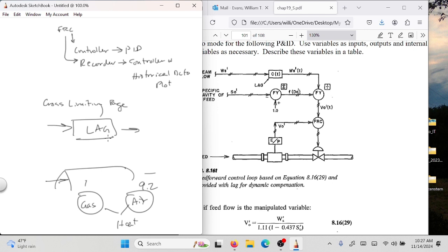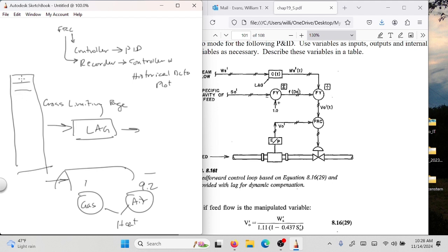How do you build a lag block if there's no such thing in your PLC? We've already talked about an instruction that works as a lag block — it's called a FIFO. Put something in, take something out, just delay it. If you want a five-second delay, put a FIFO stack in: put a value in the top, and every time you push one in, one goes out the bottom. If you have 50 of those and grab one every tenth of a second, you have a five-second lag delay.